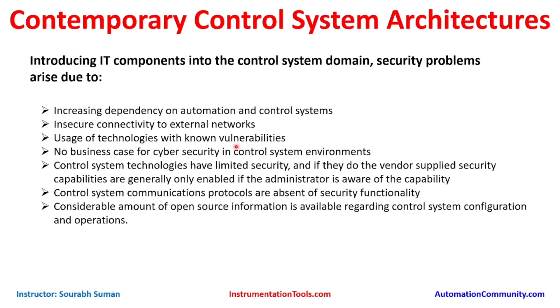Another factor is the use of technology with known vulnerabilities. Once we were so dependent on a technology, even when vulnerabilities were discovered, we were in no position to stop using it. For example, in some plants we are still using Windows XP. We cannot upgrade from Windows XP and still run the same PLC, same software, and same I/O cards, because those hardware systems were designed to work with XP. We cannot upgrade the complete plant in one go.